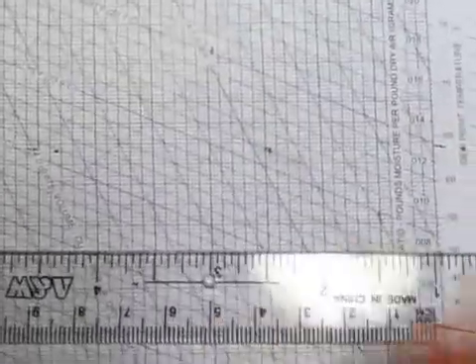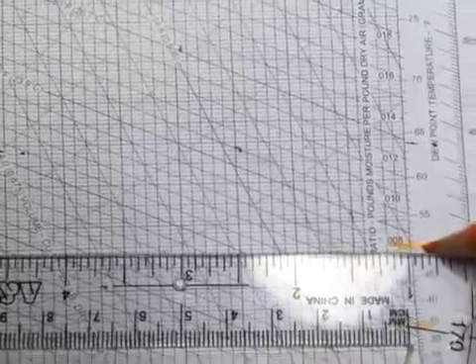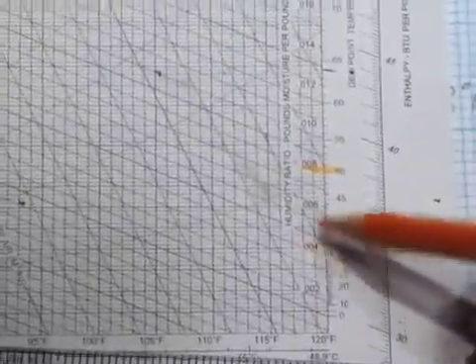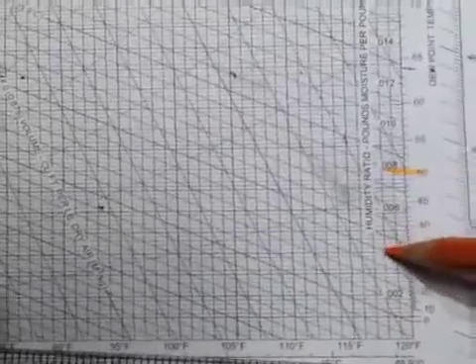But we also have the absolute humidity on the psychrometric chart of these two state points. And that difference is the amount of moisture that can condense out of, in this case, a pound of dry air. So now you can figure out how much air leakage do we have into that assembly? And that can tell you how much moisture is likely to be delivered.